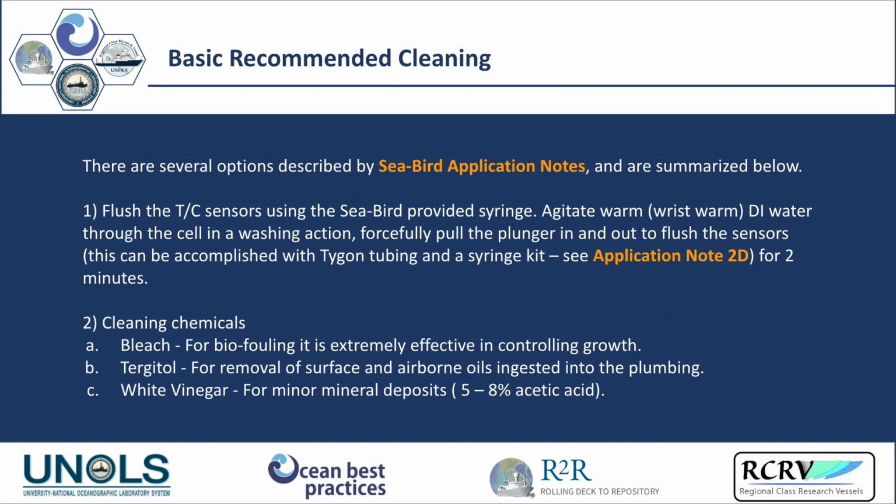These are some recommended cleaning practices that we pulled from Seabird, but also had them review all of our suggested practices. For those who are used to Triton X, the newer version is Tergitol. Triton X is no longer available internationally for standards. So Tergitol is the new one, or you can use white vinegar or bleach for very extreme cases of biofouling.